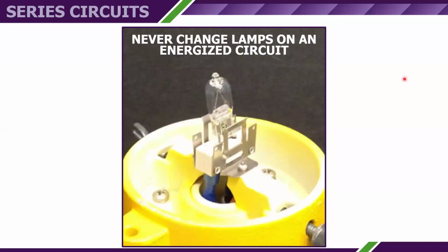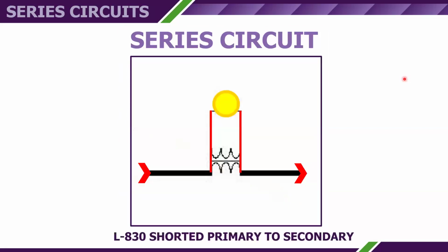Replacing lamps. What I would recommend is you drive the Airfield marking inoperative fixtures. Don't touch them, but make a mark with chalk on the pavement or something. Look for excessively bright or inoperative lights. Note any unusual conditions. If you've got an infrared temperature sensor that you can point at them, you can check the temperature of the base can and fixtures not operating. It'll be non-contact. You want to create an electrically safe work condition. Get it locked and tagged. And then just change the whole fixture. Take the other one back to the shop for repairs. Remove the marks on the fixture and restore the circuit to operation.